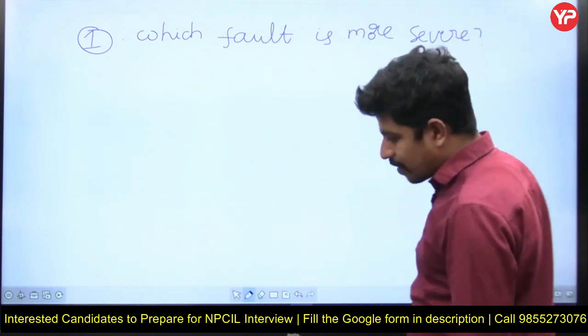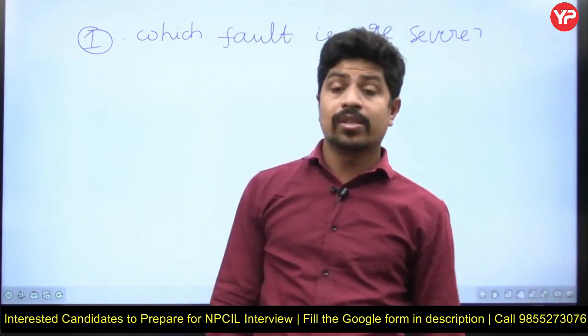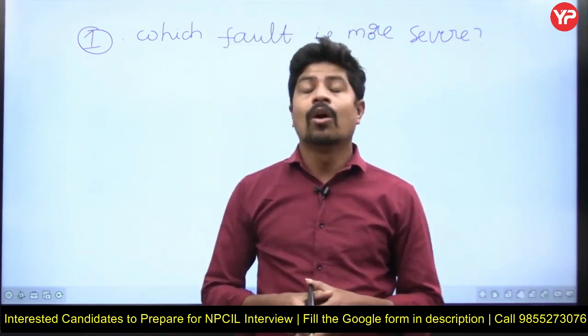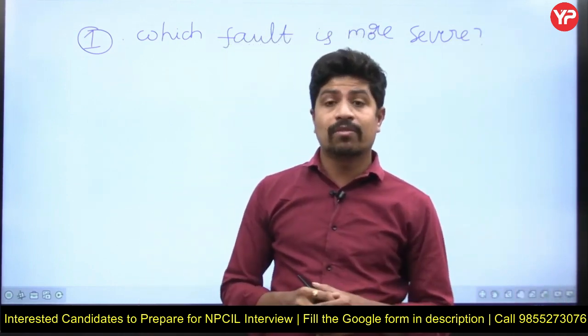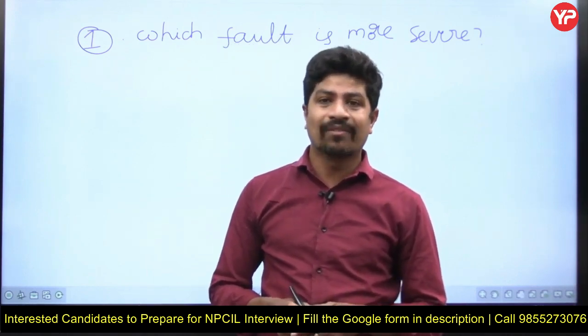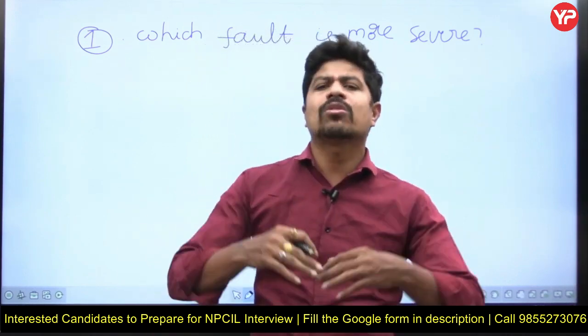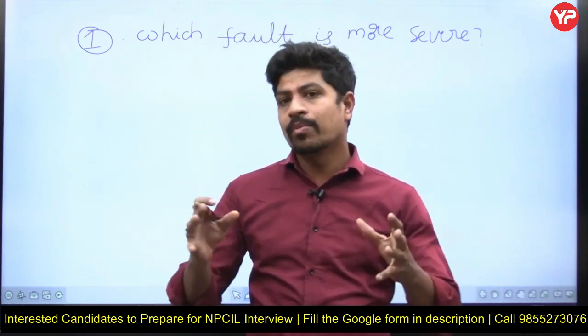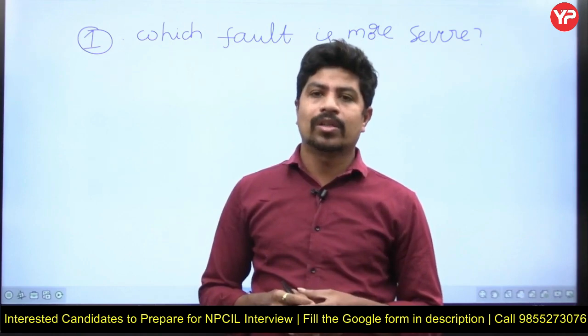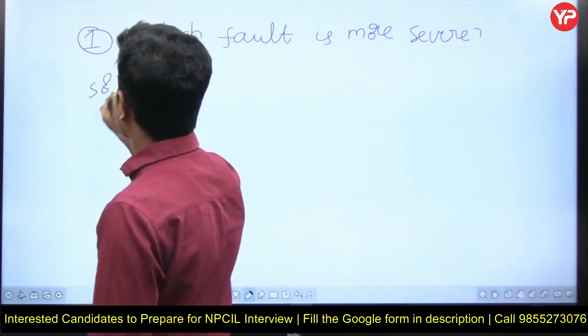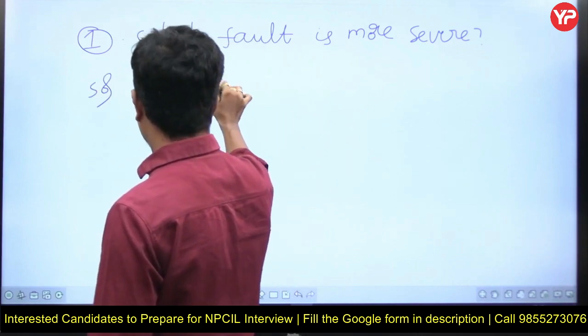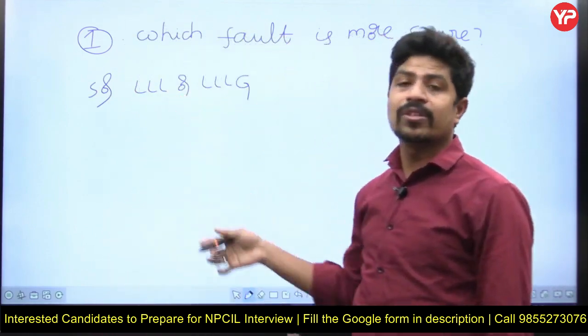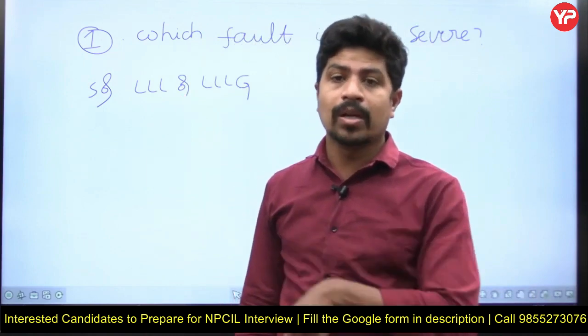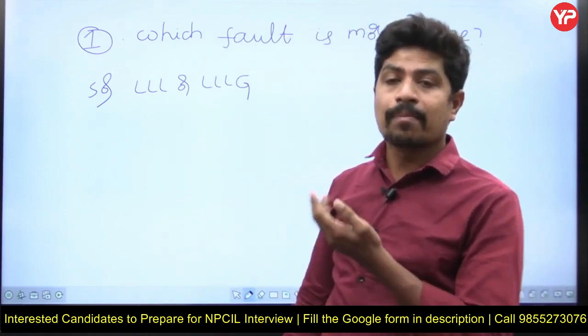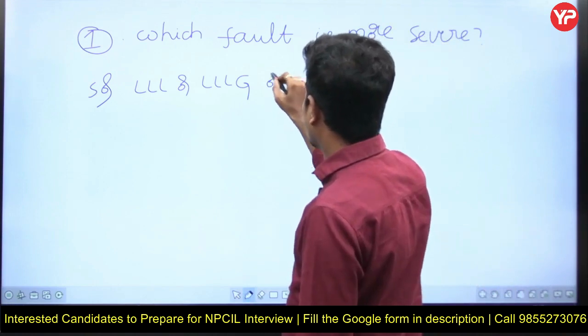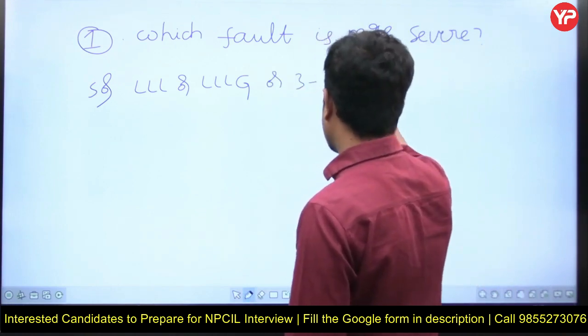Yes. First of all, one must know that the severity of a fault is decided by the fault current or the short circuit MVA. Severity of a fault is decided by fault current or short circuit MVA. Now, for this one, most of you know the answer, but how is very important. You know that it is the triple L fault. The answer for this question is triple L or triple LG. Both are the same. Physically there is a difference, but electrically there is no difference between triple L and triple LG. Why? Because both are balanced faults. Triple L or triple LG or three-phase fault is more severe.